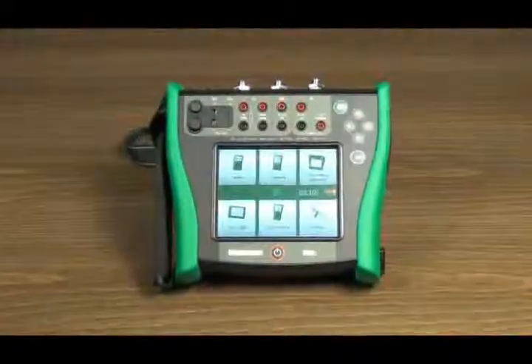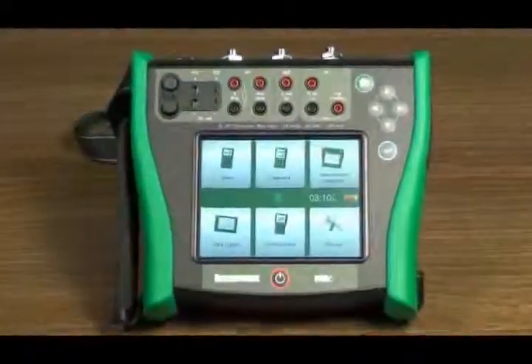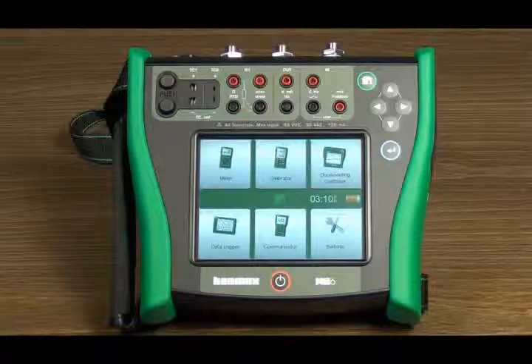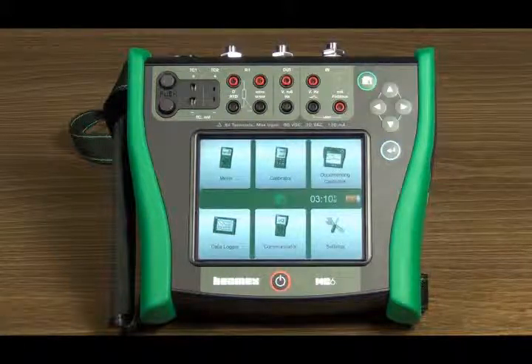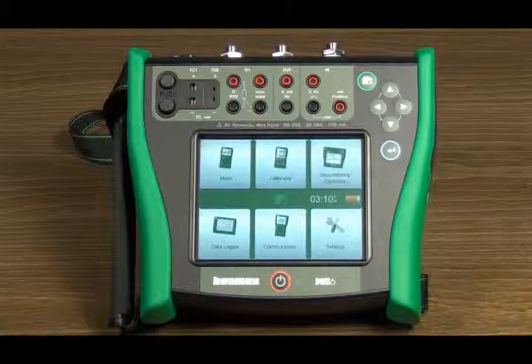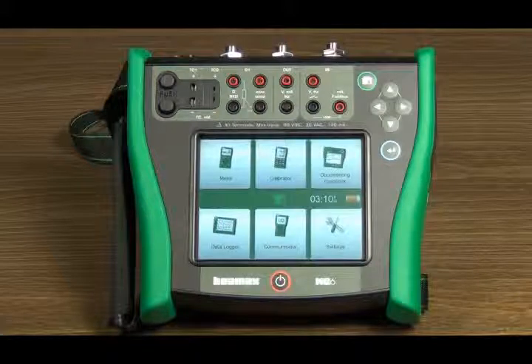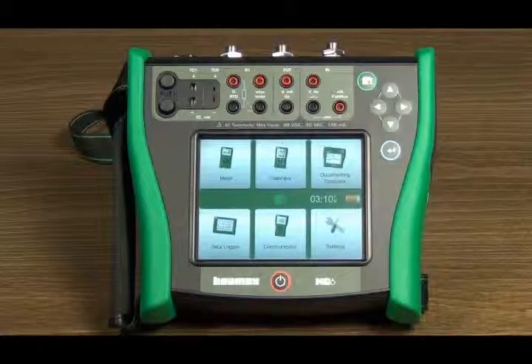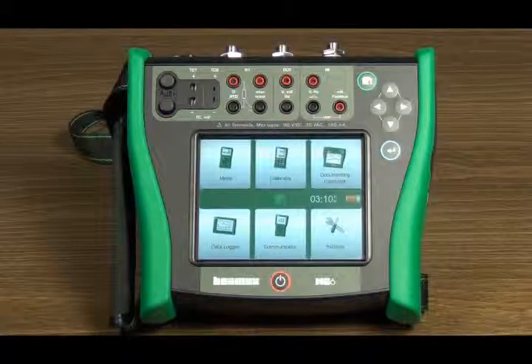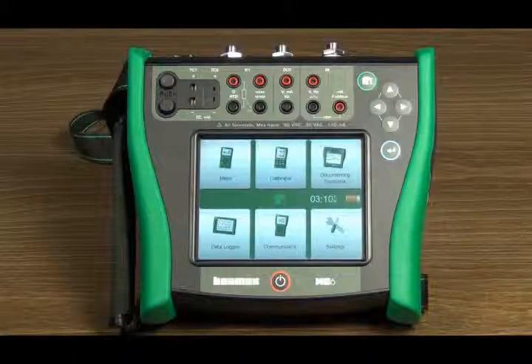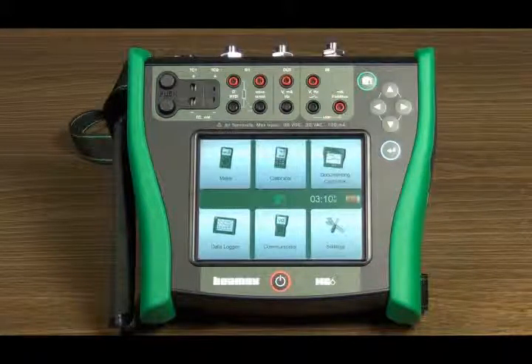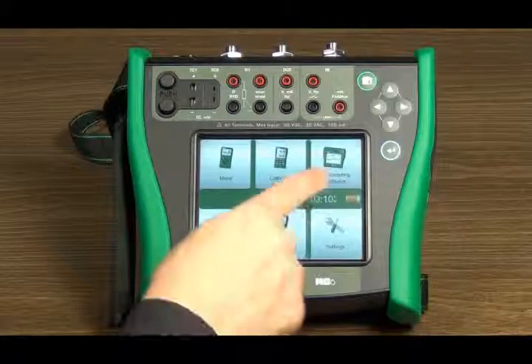The documenting calibrator mode is designed for calibrating process instruments and documenting calibration results. With the MC6 you can calibrate various types of process instruments, such as analog, HART, Foundation Fieldbus or Profibus PA. To open the documenting calibrator mode, touch the documenting calibrator icon in the home view.